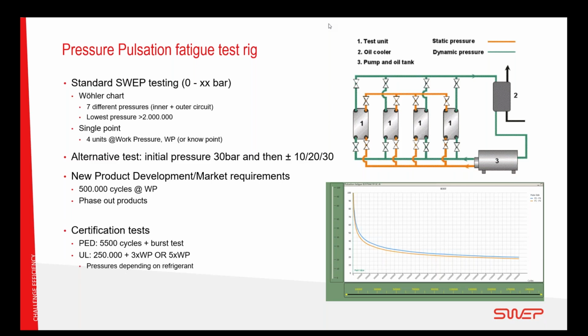You can also do single point testing, where we test the 4 units at a specified known working point, or at the design work pressure, for example. And then we get the chart shown on the lower right side here. Alternative testing can be that you have an initial pressure, and then we pulsate that pressure plus minus 10, 20, or 30 bars, for example.